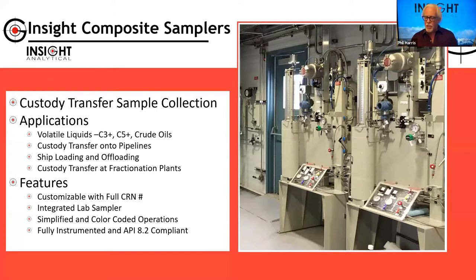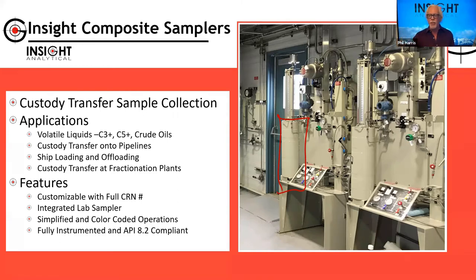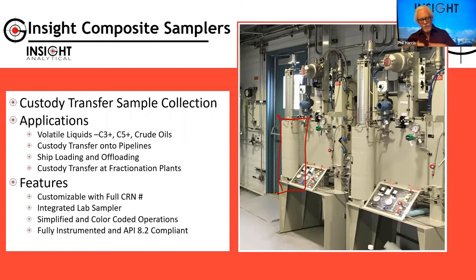So we designed these liquid composite samplers. When you look at one, you'll typically see a large accumulator vessel — like the one over there — that slowly gets filled over a period of time: it might be days, weeks, even a month in certain applications. It provides a composite or average sample of the fluid that's been flowing by. On a pipeline, for example, for every 50 barrels that goes by, we put a milliliter into that accumulator vessel.